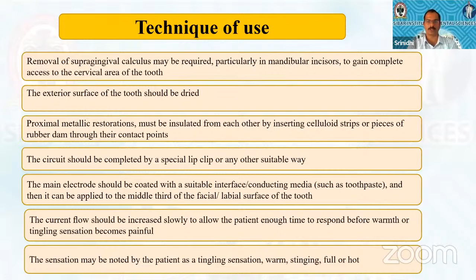The current should slowly increase. So we have a rheostat provided with the unit. We can use the rheostat to slowly increase the amount of current that is passed to the tooth. We have a number from 1 to 10, 1 to 50 or 1 to 80. That is a rheostat that is numbered. If the response is not obtained, we need to place the probe on a different location of the same tooth. So we need to change the location 2 or 3 times to ensure consistency, and an average result is recorded.